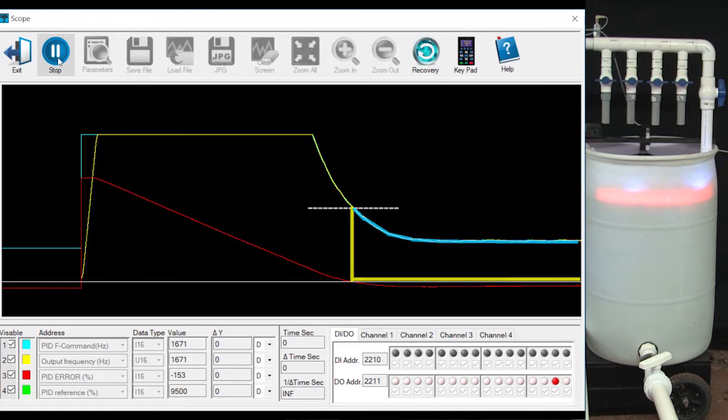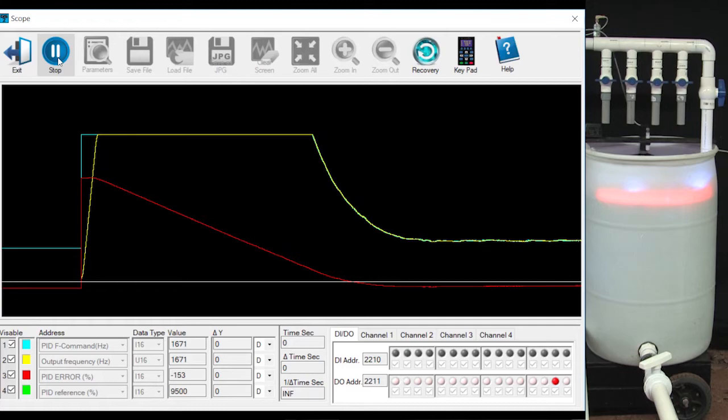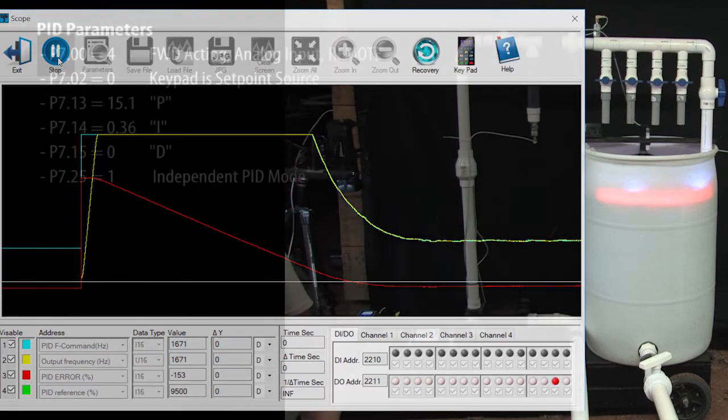And as the water level falls, sleep mode 2 waits for the PID command frequency to get large again before reconnecting it to the output frequency to the motor. That way, the drive isn't running the motor forever, burning electricity and wearing out those pump and motor parts. Let's add sleep mode to this example so we can see how it works.